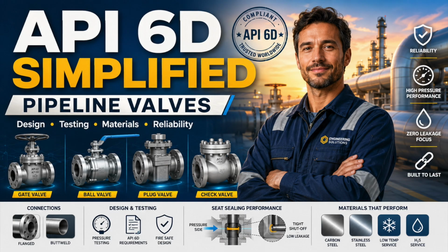This is why valve design must be documented, reviewed, verified, and controlled. A valve should not be accepted merely because it resembles something manufactured before. Similarity is not verification. Full opening and reduced port also matter far more than many procurement documents suggest. This is not only about pressure drop. It affects pigging, sphere passage, inspection tools, flow velocity, erosion, noise, and hydraulic behavior.